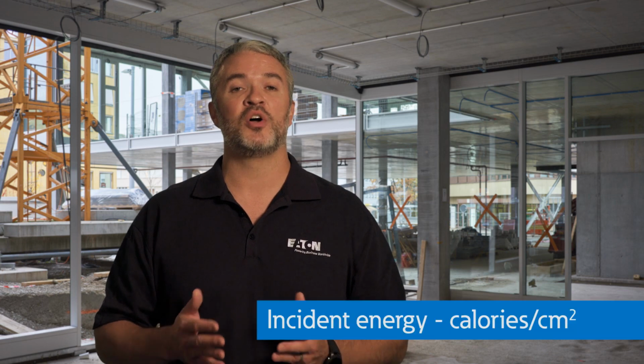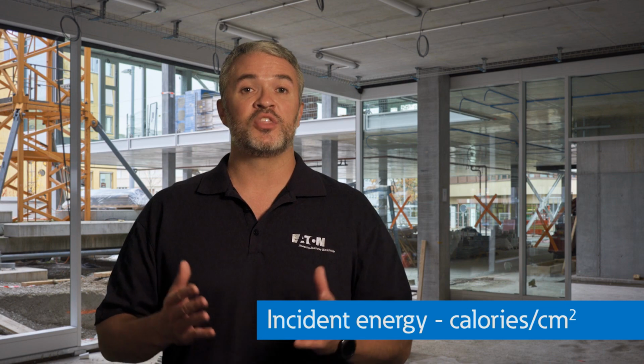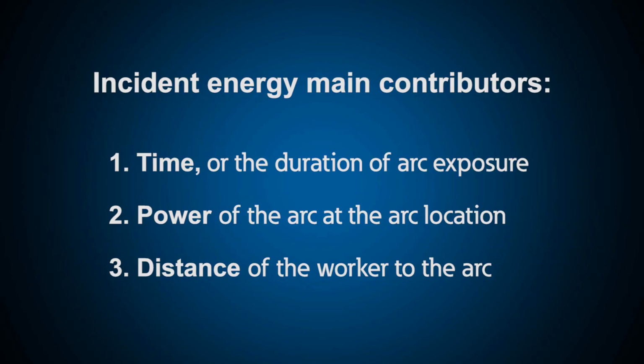Beyond the safety aspect for personnel working on the equipment, the damage to the equipment caused by an arc flash could endanger patients, doctors, and other people working in the hospital if the power system is crippled. The arc flash energy that would arrive on bare skin or on the surfaces of any garments you are wearing is called incident energy and is expressed in calories per centimeter squared. The three main contributors to determining incident energy are time, or the duration of the arc exposure, power of the arc at the arc location, and distance of the worker to the arc.